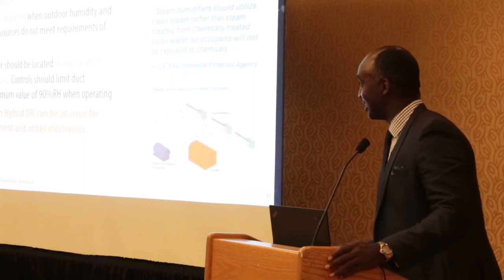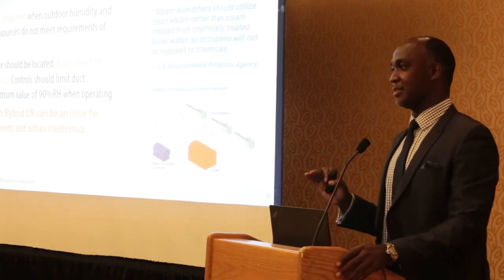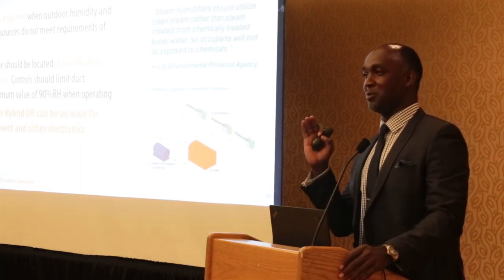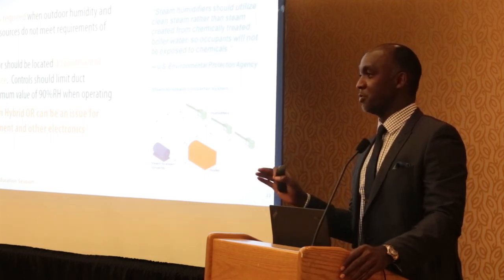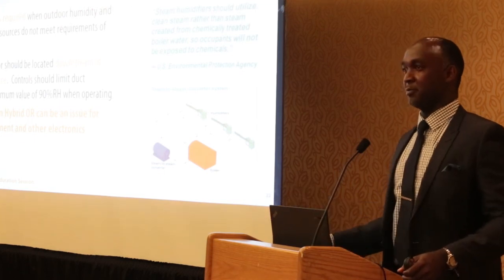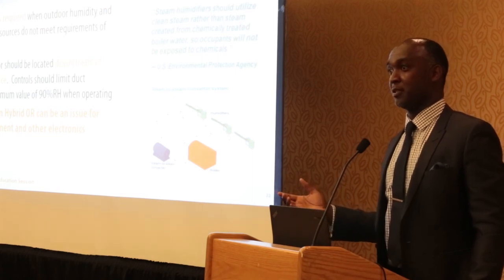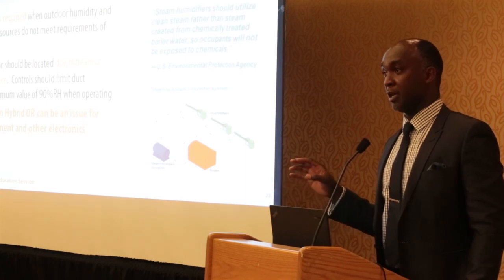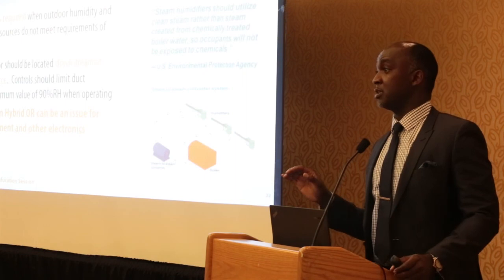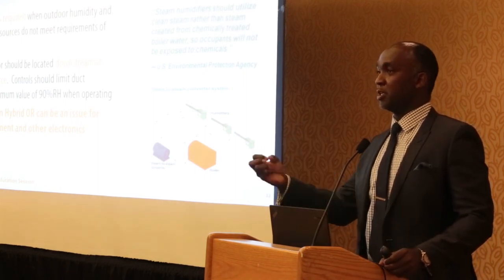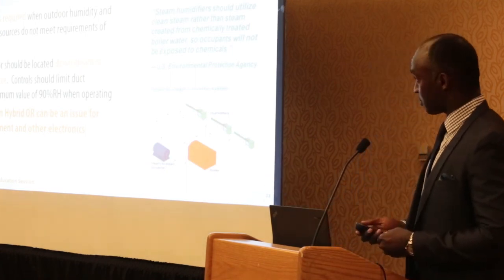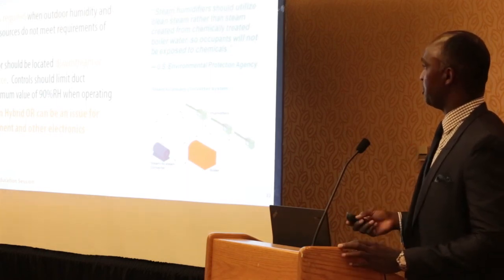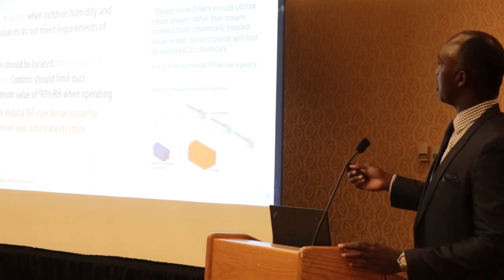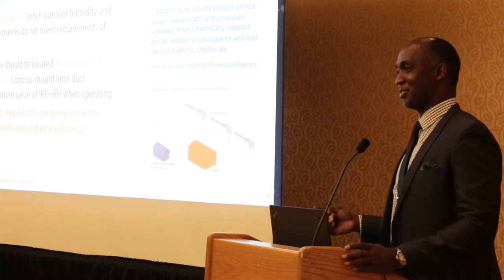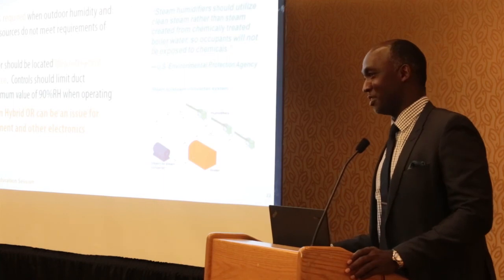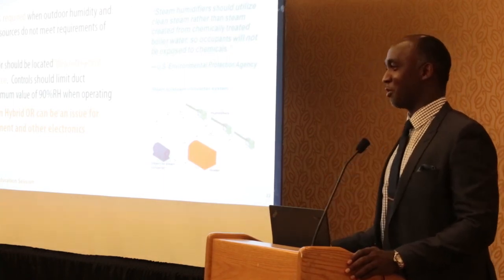Also, it talks about humidifiers. A humidifier is required in hybrid ORs because all the equipment, and even the server rooms, are very sensitive to low humidity. I don't know if you've ever been in your house and touched something and gotten that static shock. That's low humidity. So your equipment will underperform if there's low humidity within the space. You have to be very careful about the humidity setting, or whether humidity is provided as part of your system in the space. It also talks about the type of humidity used downstream, and that if you're using amine treatment in your steam system, you shouldn't have direct steam injected into your humidifiers and your system. So there's additional stuff you have to look out for when you're designing these systems.